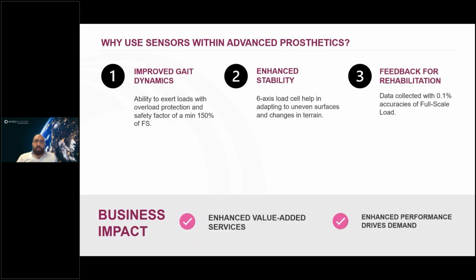patient. The strain gauges and load cell work together to analyze and replicate the natural load distribution and motion of a human foot, with overload protection and safety factor of a minimum of 150% of full scale. The load cell continuously measures the torque and multi-directional forces, allowing the prosthetic to adapt to uneven surfaces and changes in terrain. The sensor collects detailed data on walking patterns and load distribution with accuracies down to about 0.1%.